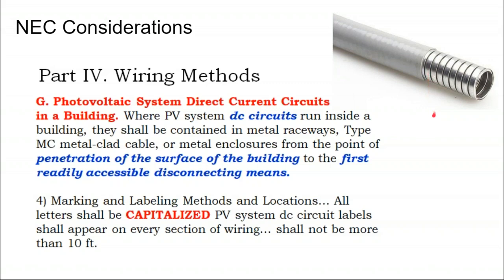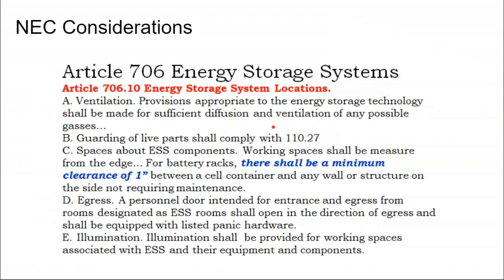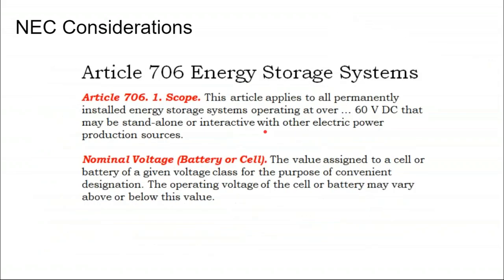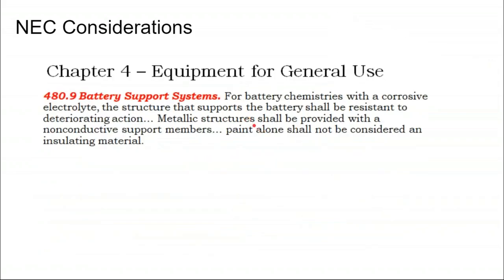If you're using metal conduit in a battery room, you'd want to paint the metal to prevent corrosion. And that's kind of why we're being reminded in our battery support system - that painted metal, you might have reason to have painted metal inside your battery room if you're building a metallic paint structure, but that paint alone shall not be considered the insulating material between the battery and the support structure.